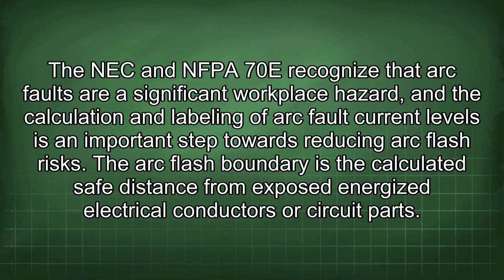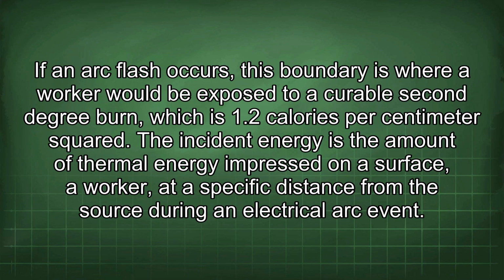The arc flash boundary is the calculated safe distance from exposed energized electrical conductors or circuit parts. If an arc flash occurs, this boundary is where a worker would be exposed to a curable second-degree burn, which is 1.2 calories per centimeter squared.